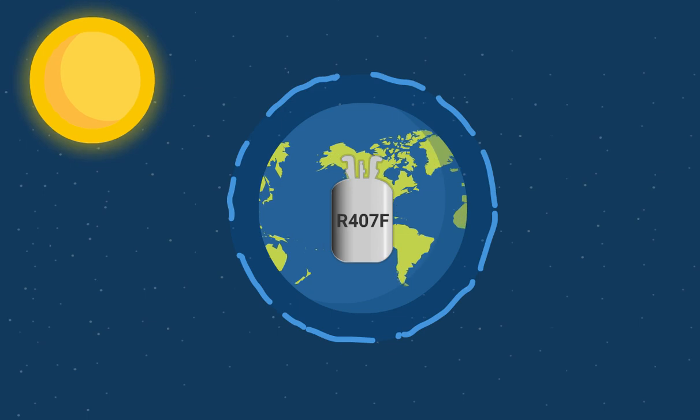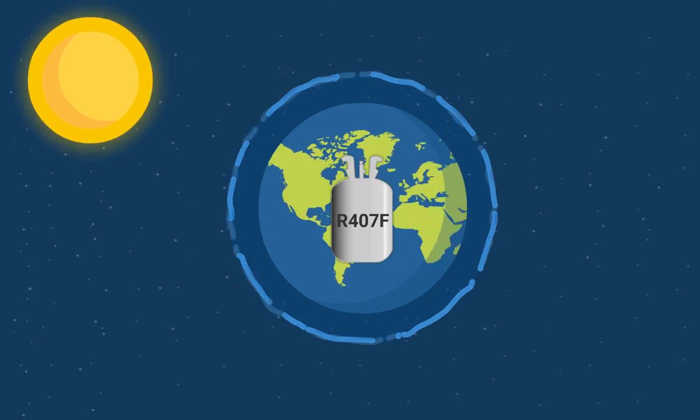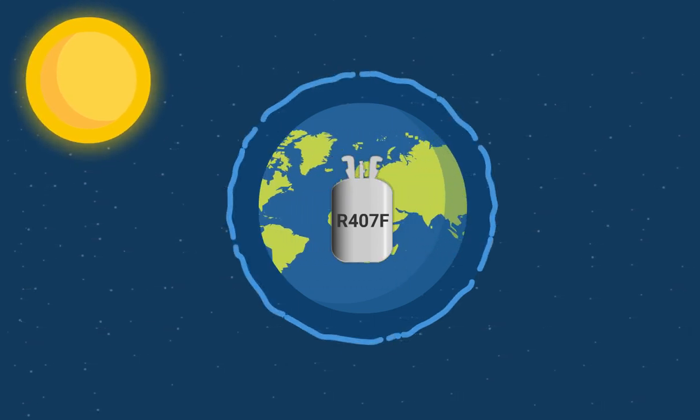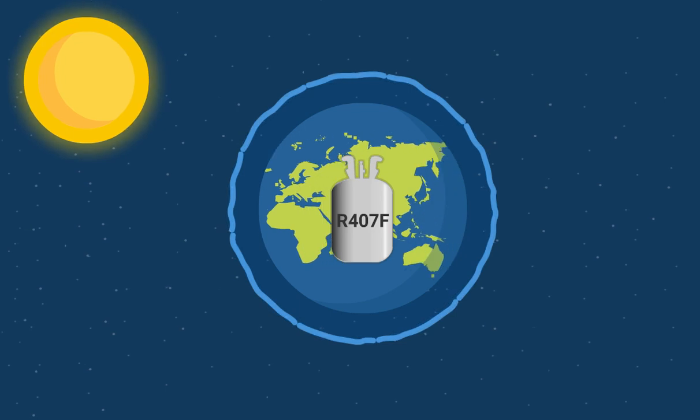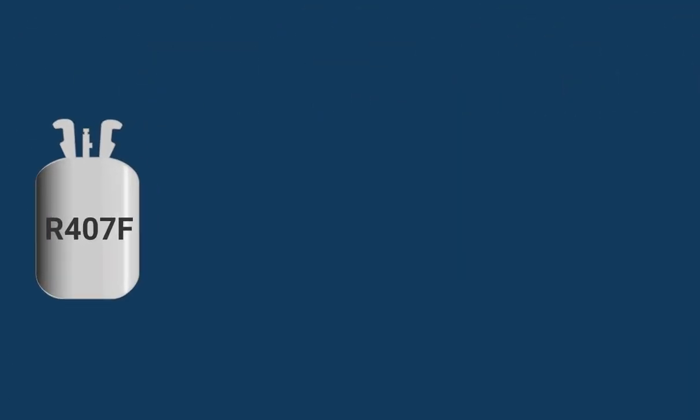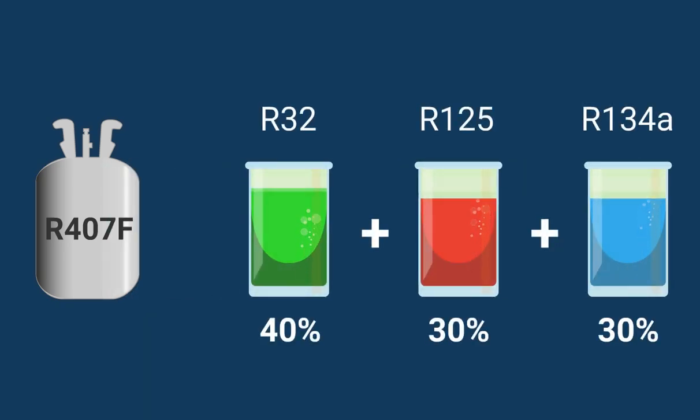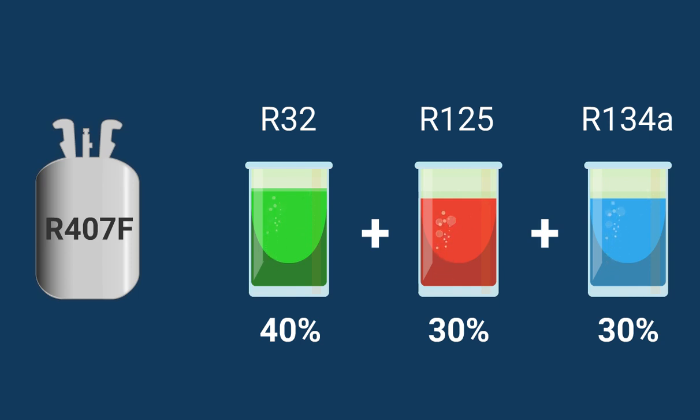Some of the replacement refrigerants are so-called blends that have far lower GWP. As an example, R407F is a blend of three known refrigerants: R32, R125, and R134A. Other blends may consist of up to five components, but the function will more or less be the same.